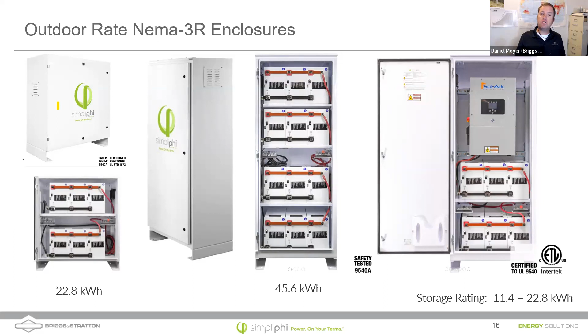If you have to, create some sort of shade structure. These cabinets do have vents for heat, and I've seen people line these cabinets with insulation for cold weather applications. Keep in mind though that equipment like that Sol-Ark you see in there, and the batteries themselves, create heat. So just because the ambient temperature is a certain temperature doesn't mean that the internal temperature of this battery cabinet or the internal temperature of the battery itself isn't going to be warmer.